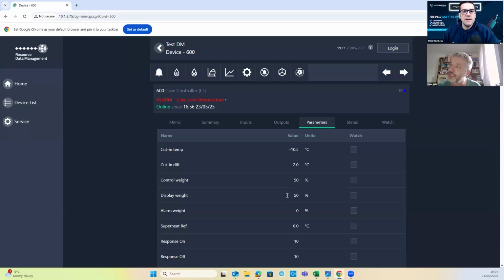The other thing you can do, let's say you're controlling on air off because it's a refrigerated cabinet. A lot of refrigerated cabinets control on air off because air on gets affected by drafts. Sometimes if the customer sees the display saying -3, because that's the air off temperature, the customer's panicking that the produce is too cold, right? So RDM lets you show a different value on the screen of the controller to what it's controlling against. So that one will be how the thermostat operates, and that will be what shows on the screen.